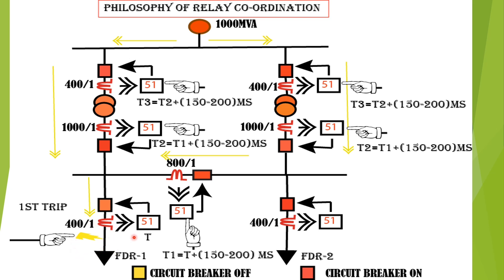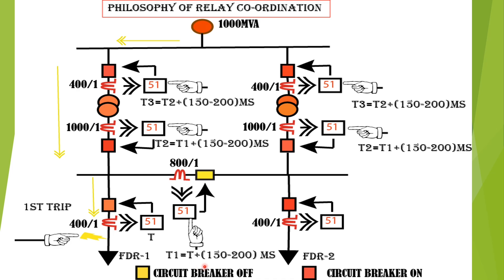Now consider that this relay is unable to clear the fault due to a breaker problem or trip circuit problem. The fault current will still flow from both sides of the transformer. After T plus 150 to 200 milliseconds, a time margin is provided for the bus coupler overcurrent relay to send a trip signal to the bus coupler breaker. Since the fault occurs in this section of the bus, after tripping of the bus coupler breaker, the fault is segregated from the bus and the healthy feeder power is not interrupted.